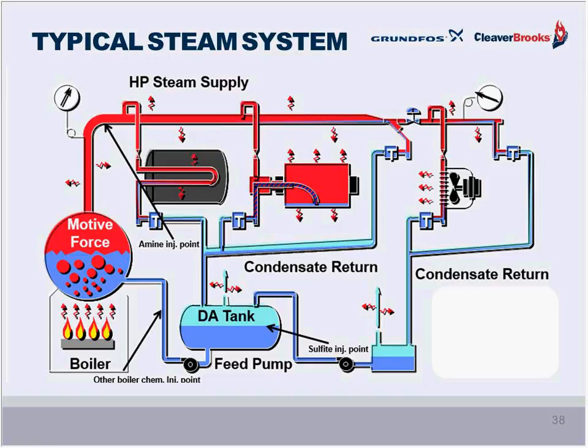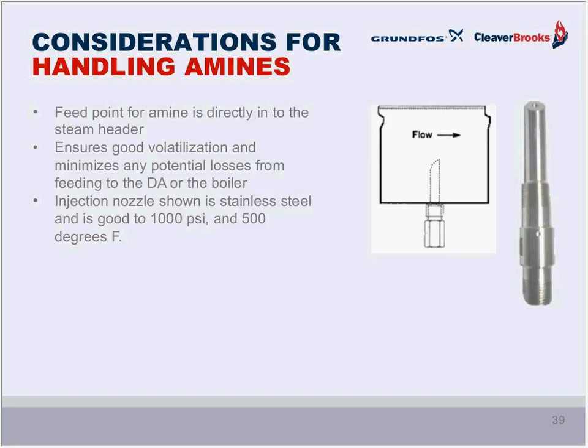Chemicals are typically injected between the feed pump and the boiler, like Steve mentioned earlier, could be polymers or even phosphate. All chemicals that we are discussing here are used in a wide variety of forms and concentrations, and these will impact the choice of pump materials and construction. I'll talk more on this a little later. Interesting is the injection of amines into the steam line. I learned a little bit through our discussions here, setting this webinar presentation up. Steve, typically chemicals are injected into a liquid process line, and in boiler systems, the injection of amines is an exception. The reason for injecting into the steam line is to ensure good volatilization of the amine solution and to minimize potential losses that occur by injecting into the DA tank or boiler directly.